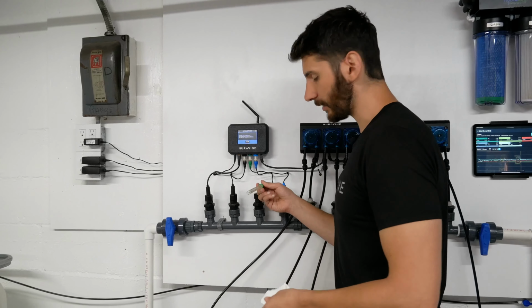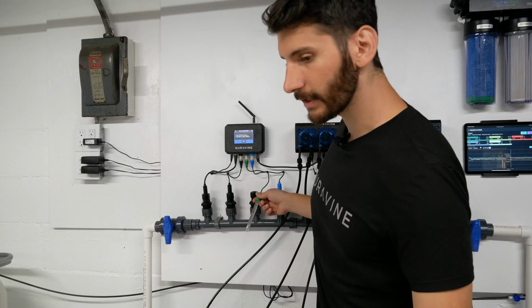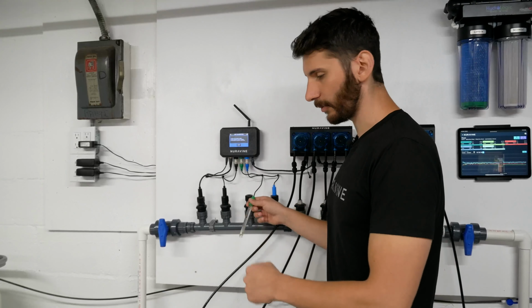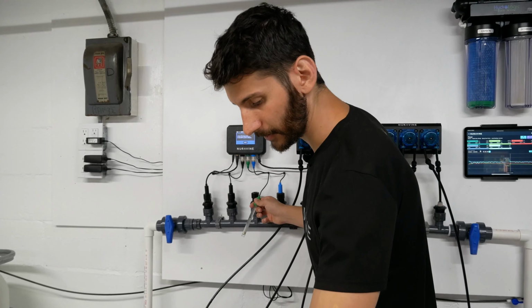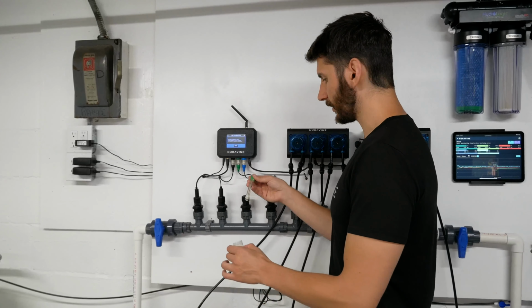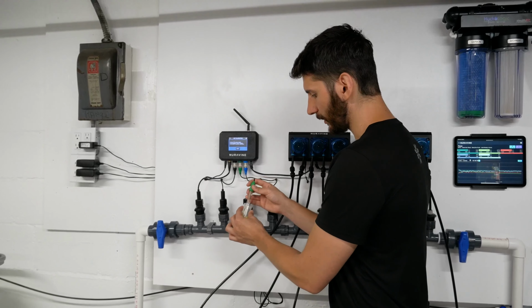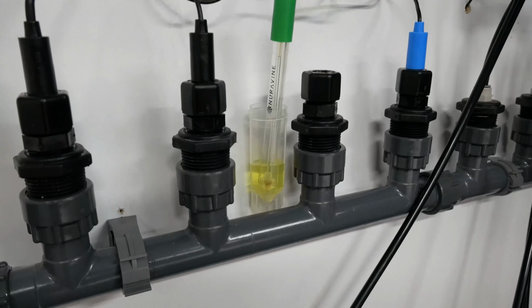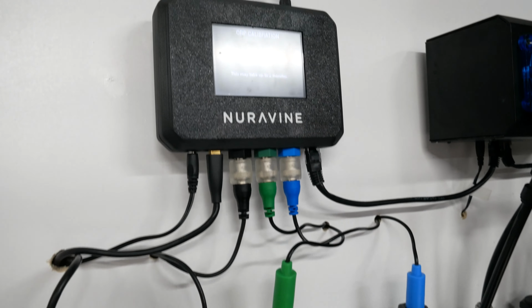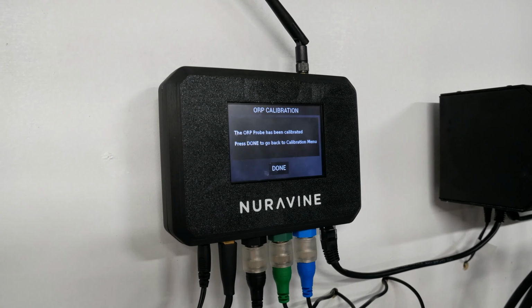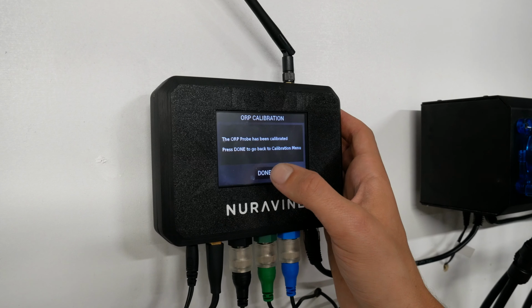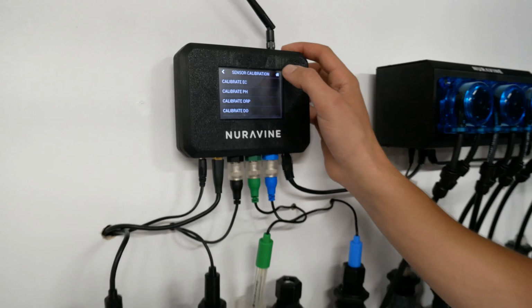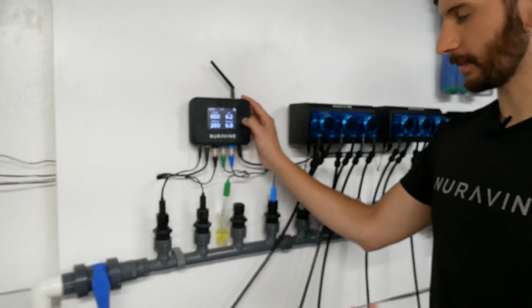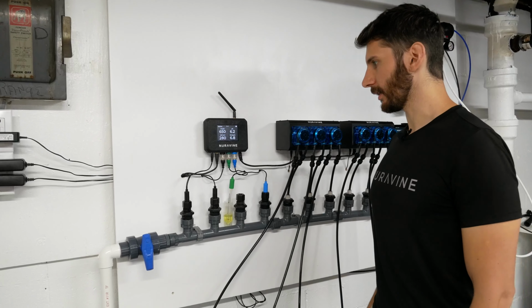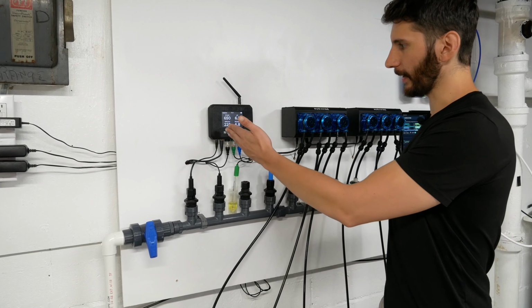Tap it. This one is sort of delicate, not quite as delicate as the pH, but definitely more delicate than the EC and dissolved oxygen. So what we're going to do now is simply put this probe into the solution, and then we're going to hit next. All right, so now that this is done, we're going to hit the done button, and then we're going to go back to the home screen to confirm our calibration. So after a few seconds, this should read about 220.